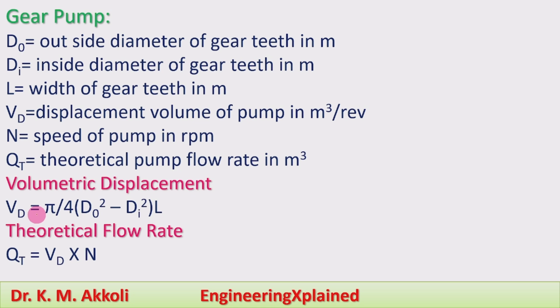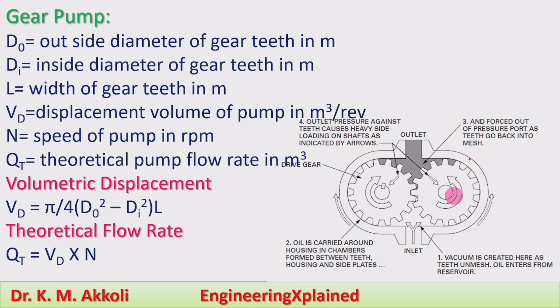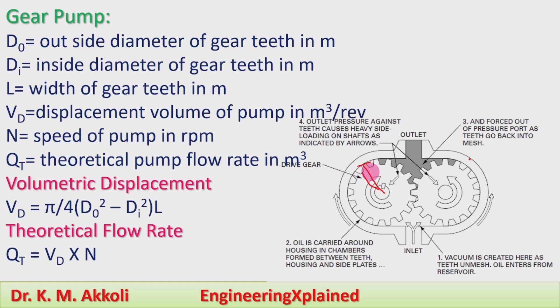The volumetric displacement is multiplied by the number of revolutions to get flow rate. D0 is the outside diameter of the gear teeth, and Di is the inside diameter. The cross-sectional area is π·D0²/4 for the outer circle, and π·Di²/4 for the inner circle, and the inner area is subtracted from the outer area.